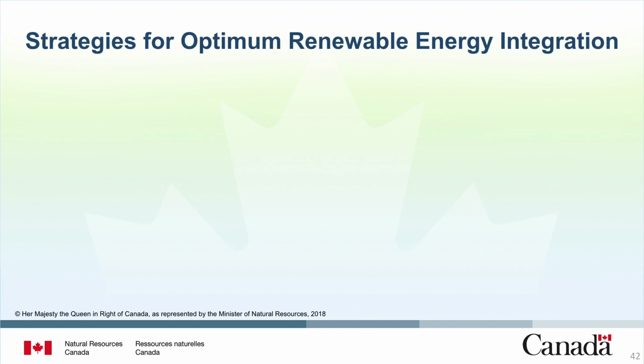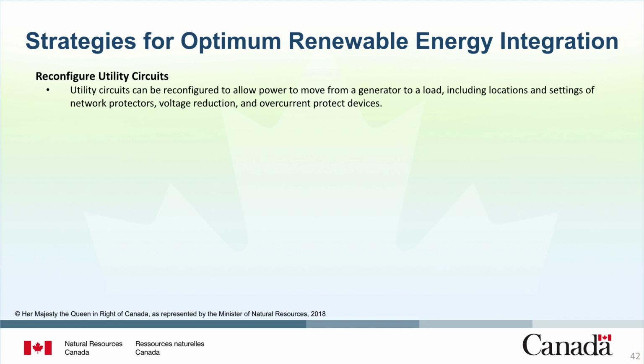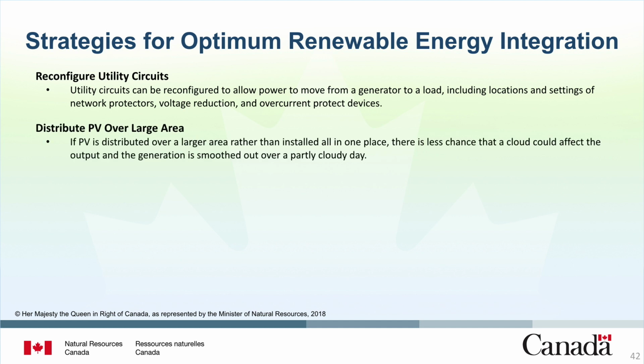To begin this segment, let's discuss some of the key strategies to increase intermittent renewable energy generation to an existing distribution system. The first strategy is to reconfigure utility circuits to allow power to move from a generator to a load, including locations and settings of network protectors, voltage reduction, and overcurrent protection devices. The second strategy is to distribute PV over a larger area. If PV is distributed over a large area rather than installed all in one place, there is less chance that a cloud could affect the output and the generation is smoothed out over a partly cloudy day.